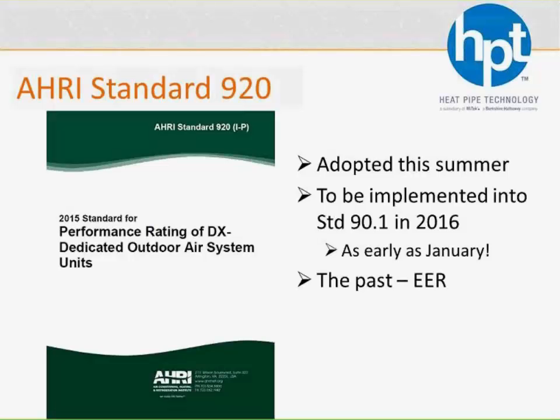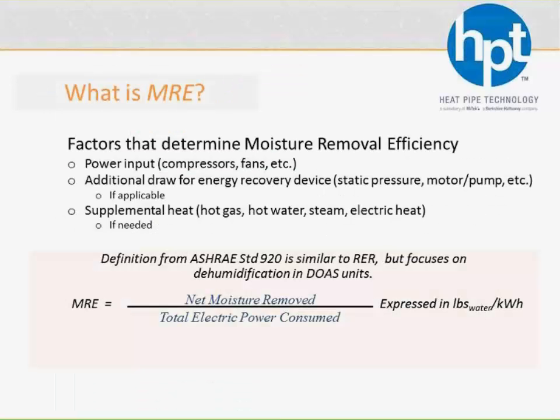Well, up to this point, DOAS equipment, like all other cooling equipment, the only way to rate efficiency has been through EER, or a version of kW per ton. But a big difference between DOAS equipment and other cooling equipment, like chillers, where the main focus is reducing load or cooling a load, is that the main purpose of the DOAS unit is controlling humidity or removing moisture. So 920 sets a standard on a new metric they call MRE. And EER is going to go away as a measuring point for DOAS units, and from now on it's going to be focused on MRE.